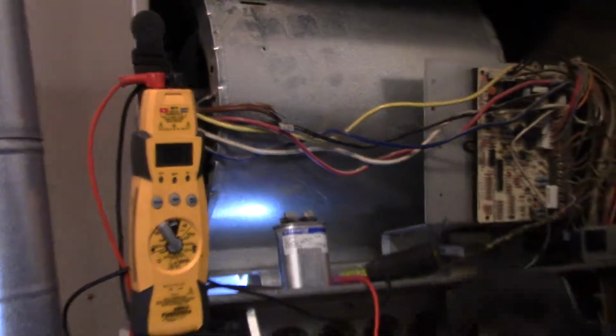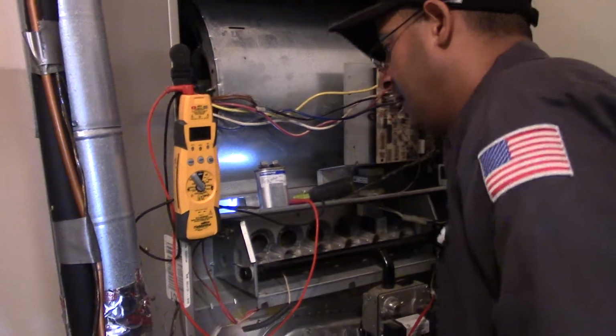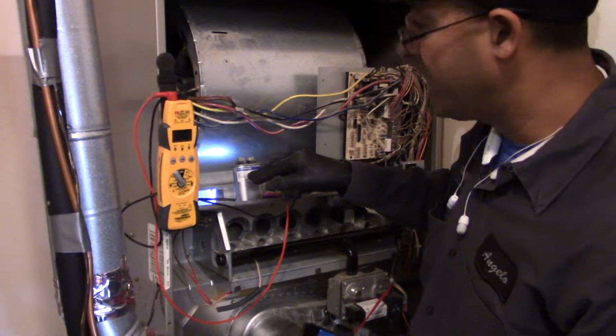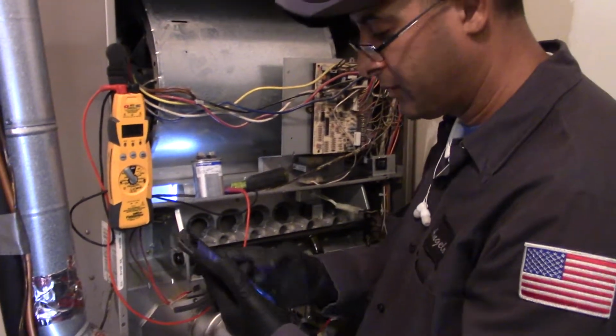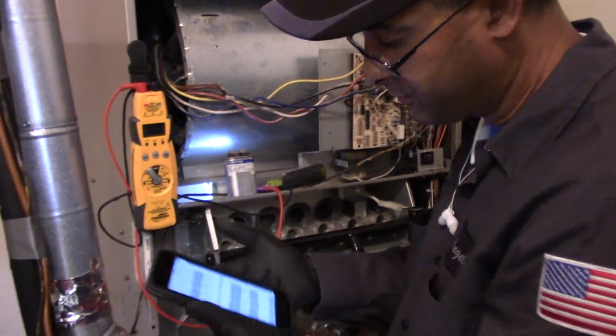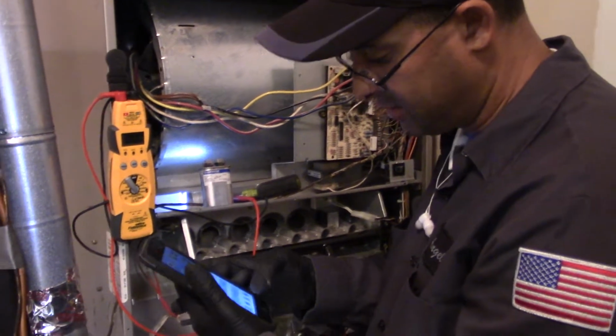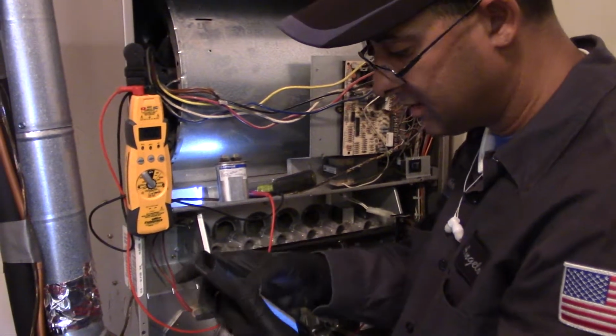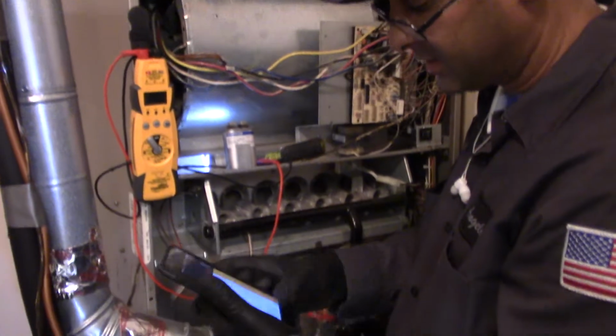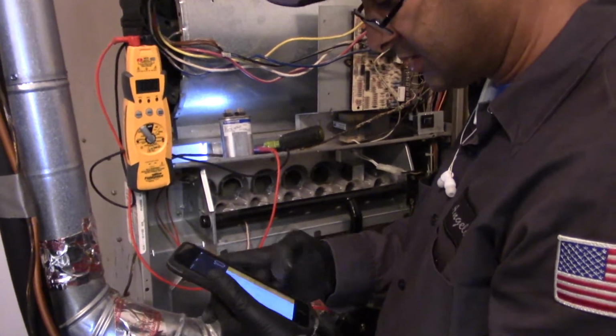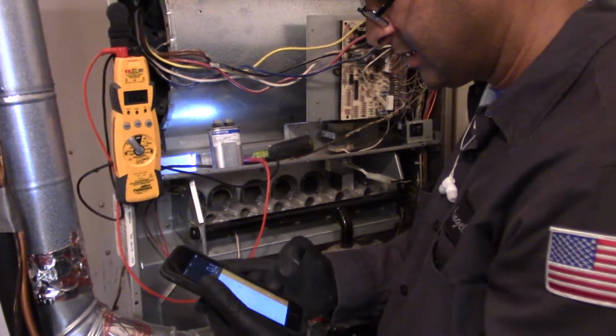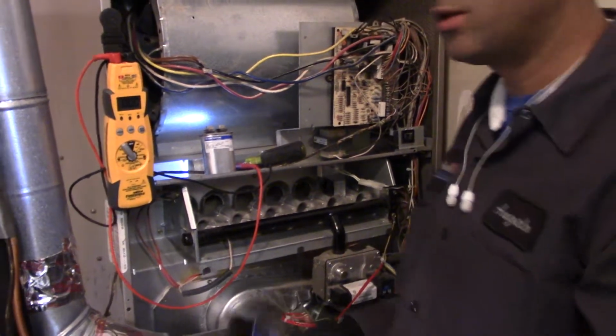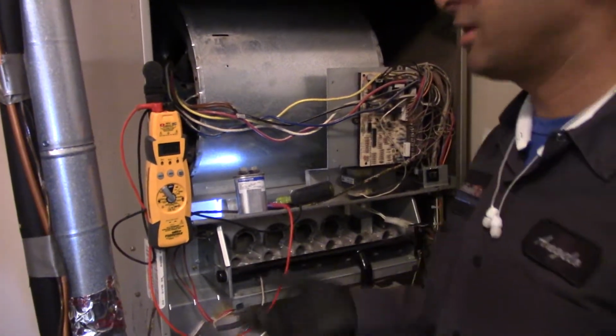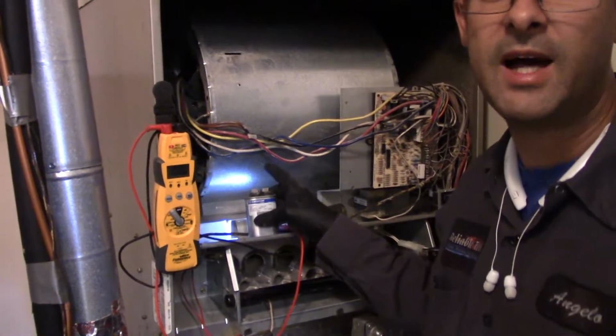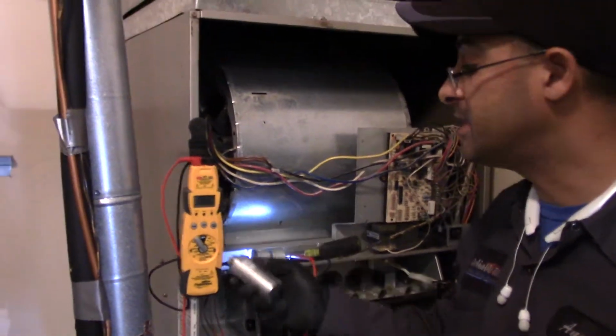So then what I'll do is go ahead and go to my calculator. This says 10 UF, but it's reading 9.2, and I know it's supposed to be within 6% of range. So if I have 10 minus 6%, that equals 9.4. So it's under capacitance, and I'm going to go ahead and recommend replacing this capacitor, because I could be saving the motor.